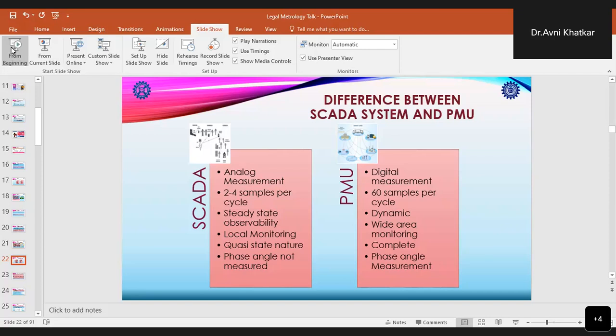So when we use a normal 104 RTU in the SCADA system, it will send readings every few seconds. And it can be used to read the voltage, current, frequency, breaker status, etc. in a substation. However, due to its very quasi-static nature, it cannot be used to read or compare phases, that is the phase shifts in the grid. So a SCADA system which is built on this cannot be used to reliably monitor the health of the grid and to isolate the trouble spots of the grid.